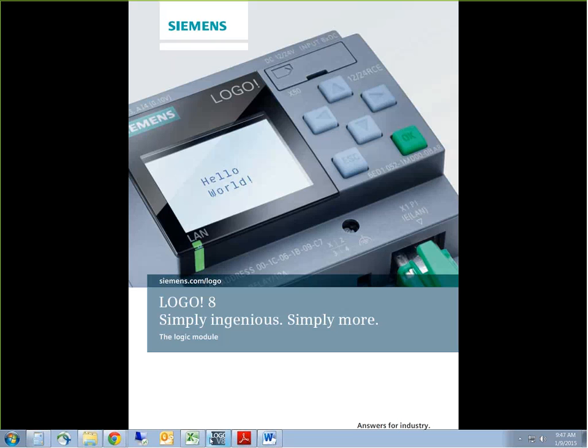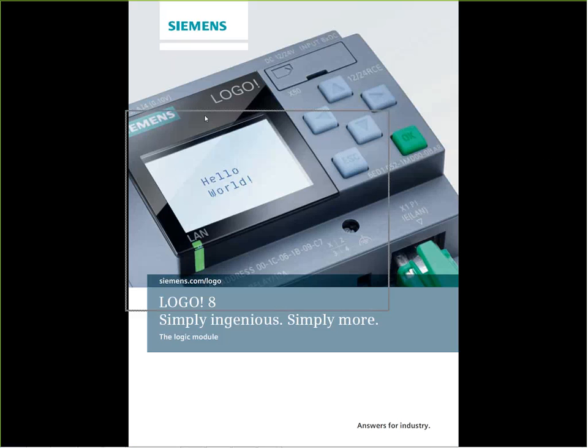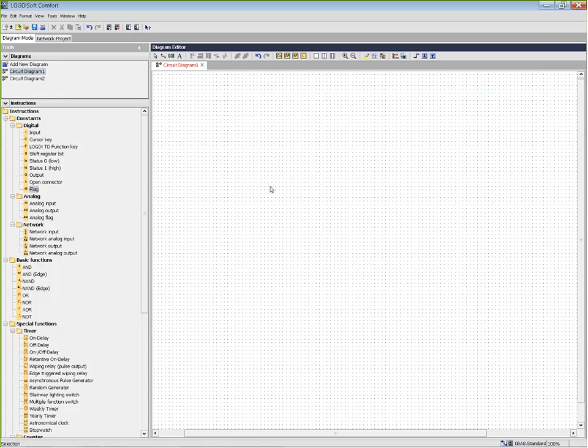In fact, that's one of the hidden advantages of Logo, its Logo Soft Comfort. Let me show you that. So here it is. To program the Logo, it's kind of a hidden gem in the automation industry. We just take inputs, stick them up on the screen. If I take an output, stick it on the screen, we just tie them together, and I've just created a relay. So when the input's on, the output's on. Logo has four 10-amp relay contacts on it, so we've actually created a relay right there.